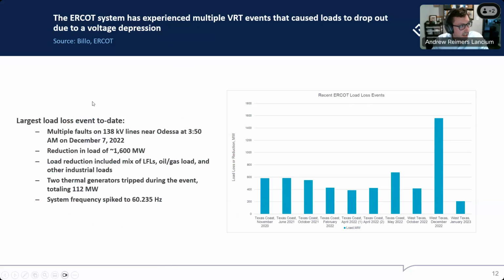Similarly, another slide from ERCOT, this one from Jeff Bilo, showing load loss events due to voltage instability issues. The largest of these being this 1600 megawatt event in West Texas, where a voltage drop on the system caused some 1600 megawatts of load to drop off. And that caused a frequency spike. And this is only 1600 megawatts, and we're talking about much, much more capacity on the system that could be susceptible to these kinds of events. That is the real concern: if system operators don't get a grip on these kinds of issues, the reliability issues are just going to get a lot worse.